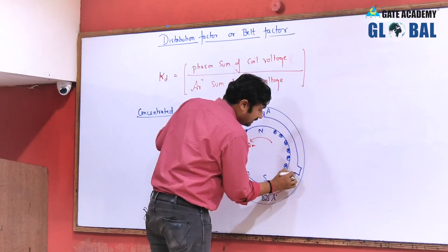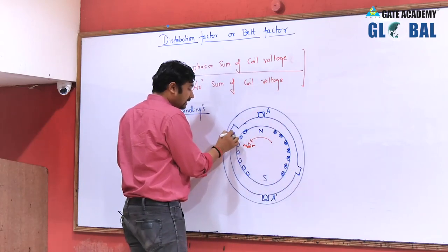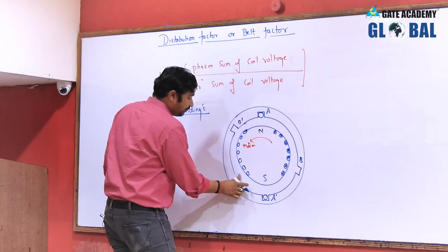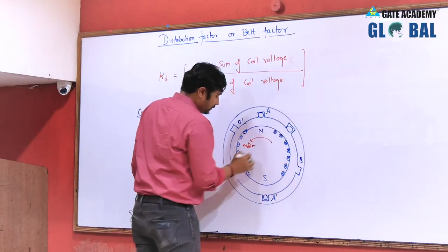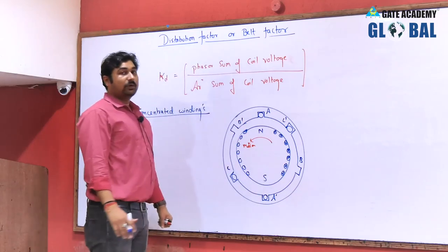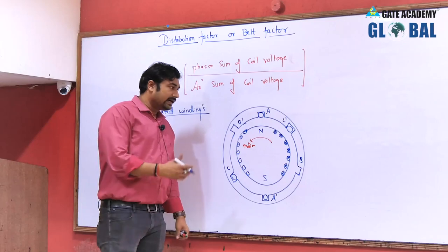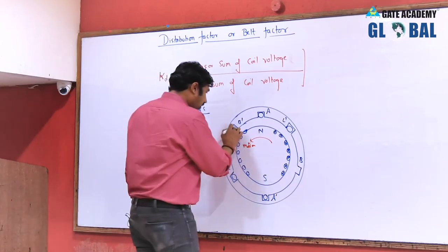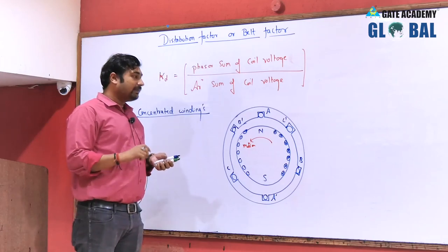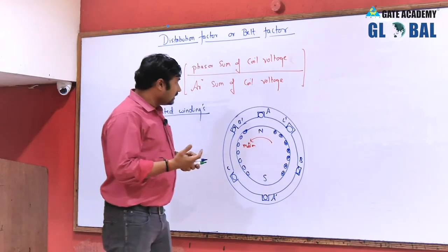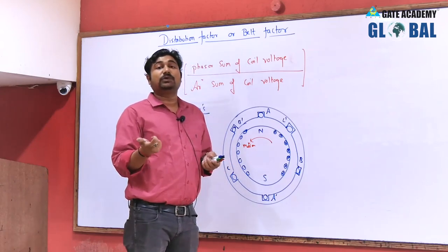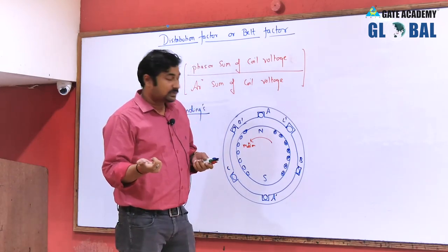Similarly, the entire B phase winding is concentrated in slots B and B-dash, and the entire C phase winding is concentrated in slots C and C-dash, where C represents group 1 conductors and C-dash represents group 2 conductors. This is what we call concentrated winding. However, in actual practice, the coils are not concentrated but are distributed into a number of slots, and the induced EMF develops in each coil is phase-displaced by angle beta, the angular displacement between the slots.